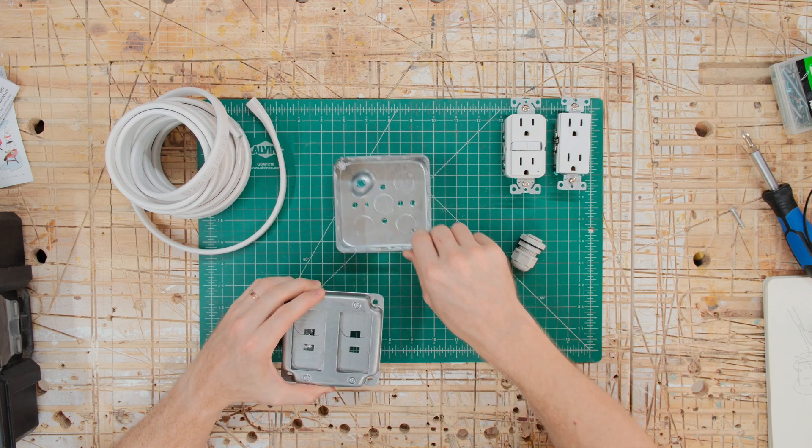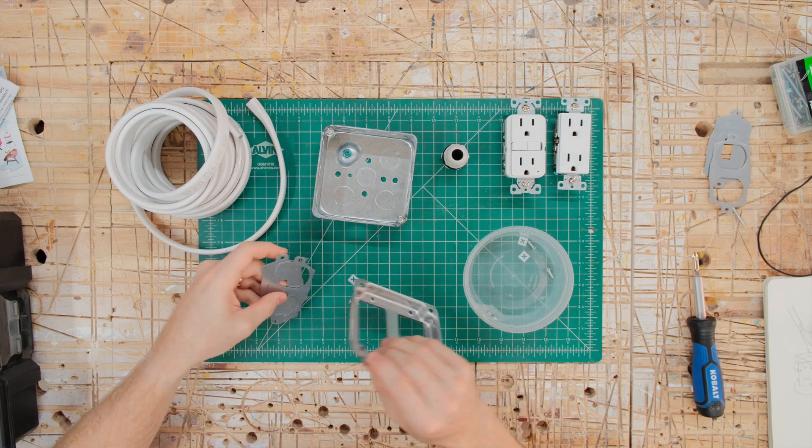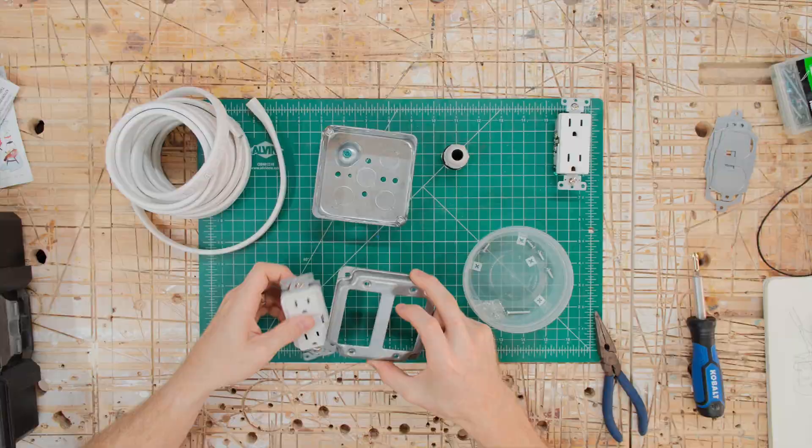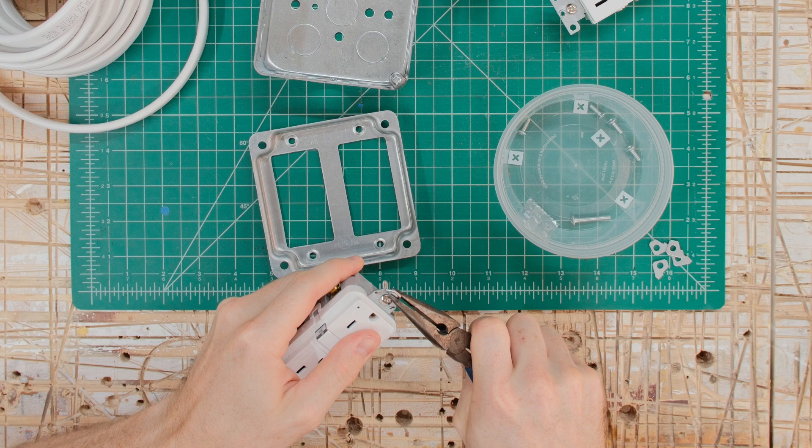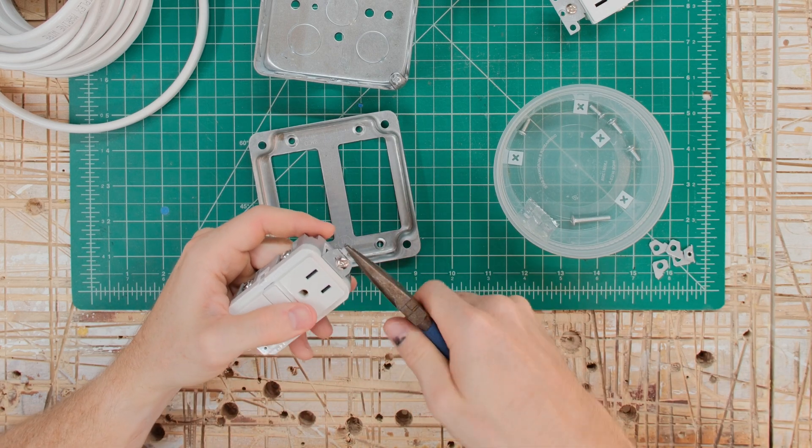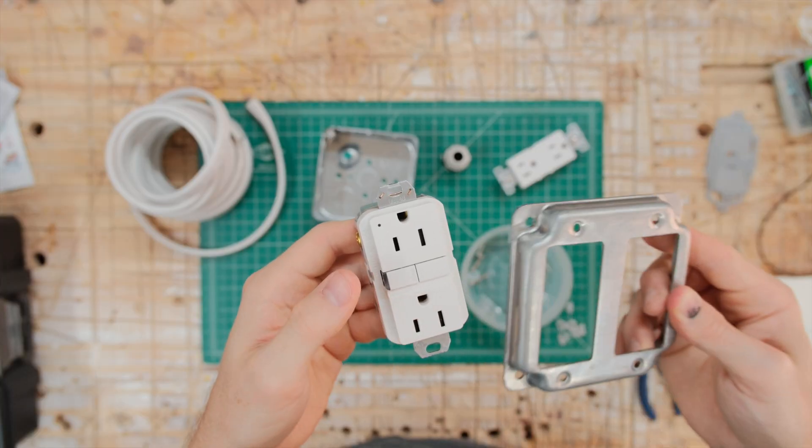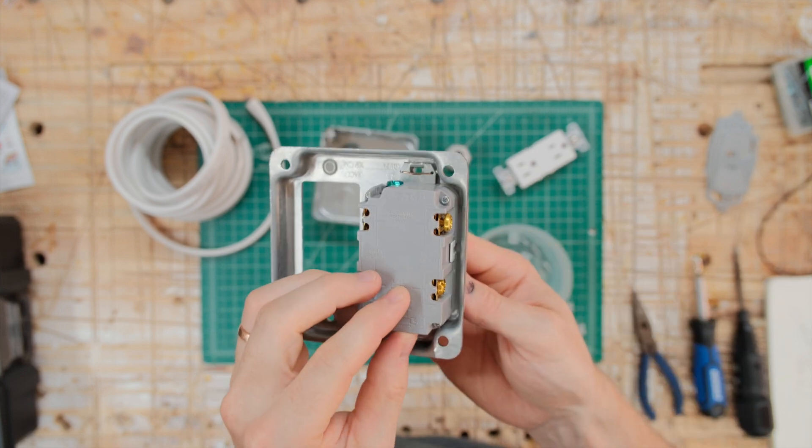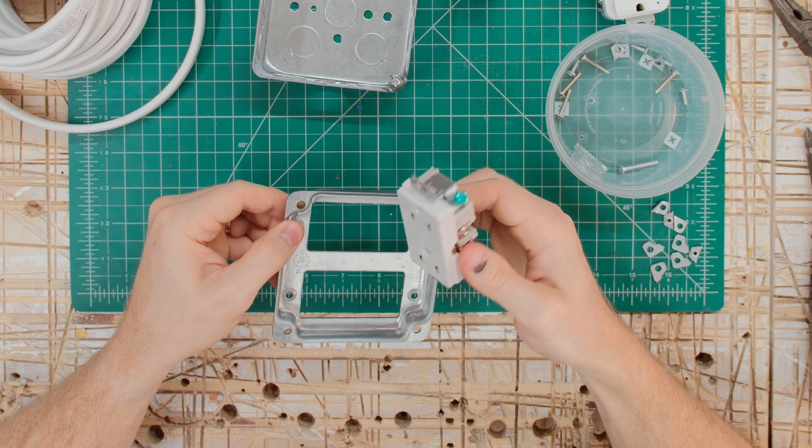With this type of outlet box, the receptacles attach to the cover plate with a small nut and bolt rather than attaching to the box itself. In order for them to fit into the back of the cover plate, you have to break off the ears or mounting tabs at the top of the receptacle. You can do this by bending them back and forth with a small pair of pliers. But make sure you buy outlets where these tabs are already punched out to break off easily. Once they are off, the receptacle can fit into the cover plate like this. We don't need to bolt it on yet, just make sure it fits. Repeat this for the second outlet.